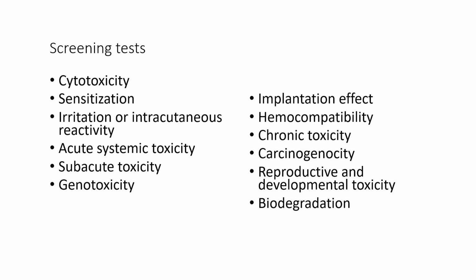Okay, so what are some of the screening tests for biocompatibility? There are several terms and terminologies which are often observed, which include cytotoxicity, sensitization, irritation or intracutaneous reactivity, acute systemic toxicity, genotoxicity, right? Then we have implantation effects, hemocompatibility, which has to do with blood, and chronic toxicity, whether this is leading to long-term toxicity, right? Carcinogenicity, whether any of this has the possibility of causing cancer.